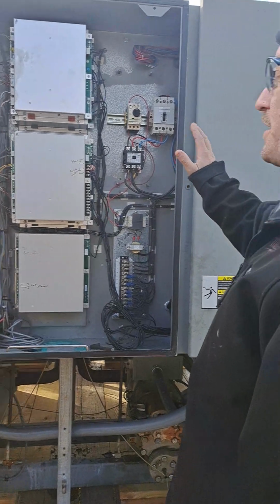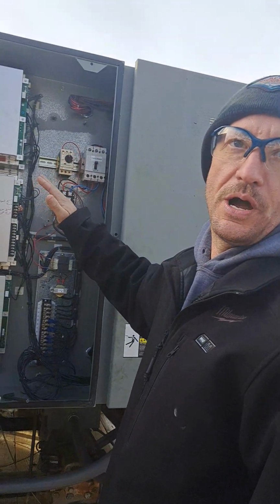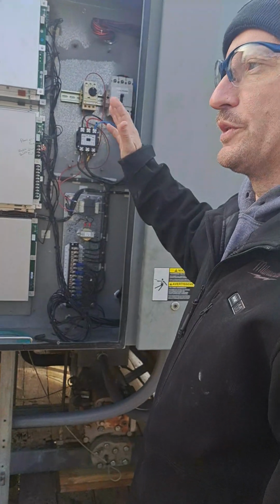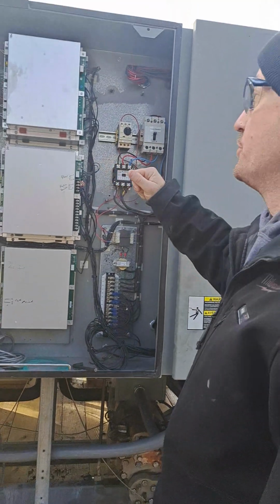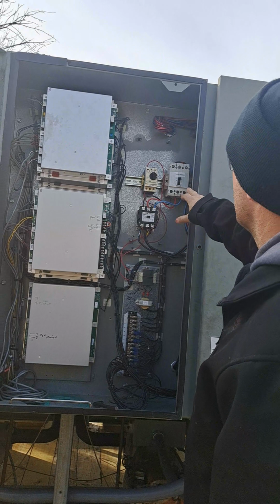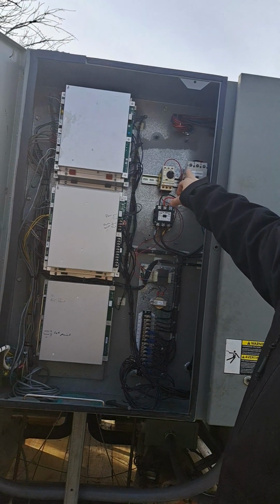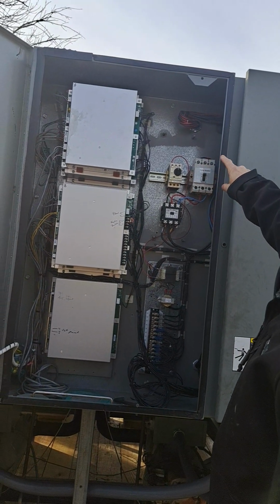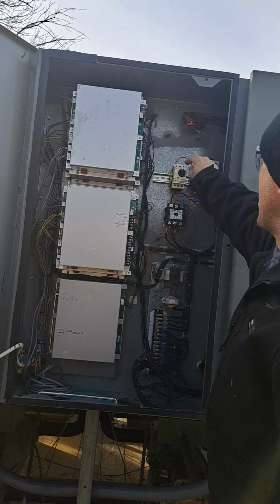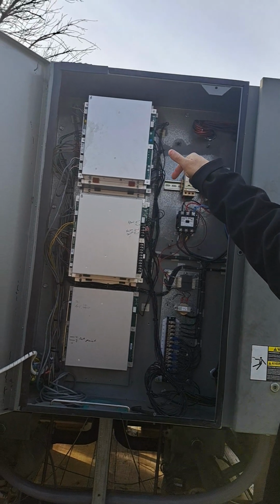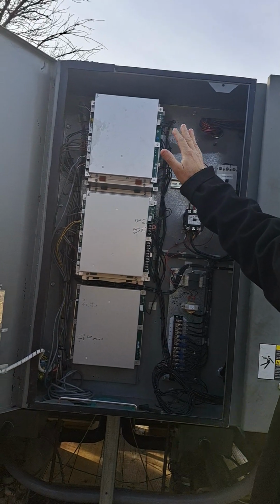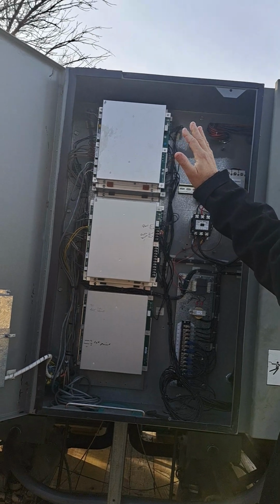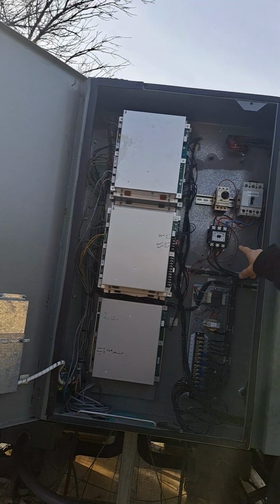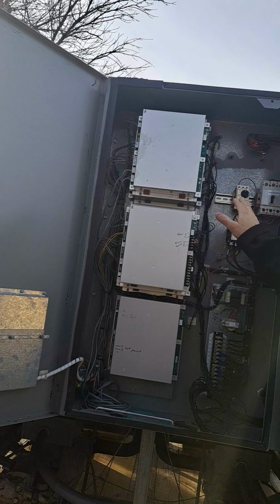Kind of crappy the way they installed this. This isn't really the way it should have been done, but that's what they installed for a switch on it. So this is a circuit breaker for the pump. If you need to service the pump, turn that off, shut off that breaker, and then you can take the motor out and work on it and stuff like that. Okay. So this is your pump contactor. This is what starts and stops the pump.